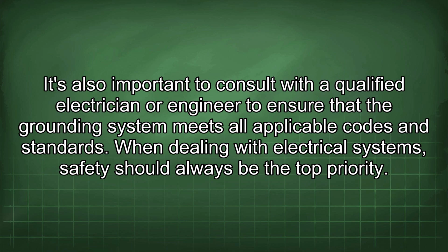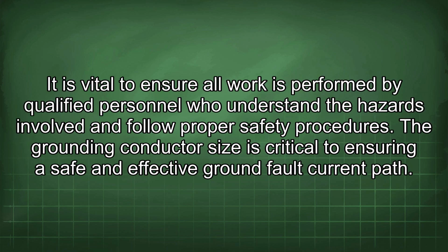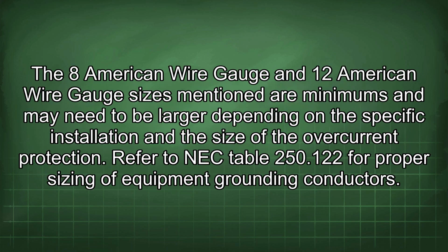When dealing with electrical systems, safety should always be the top priority. It is vital to ensure all work is performed by qualified personnel who understand the hazards involved and follow proper safety procedures. The grounding conductor size is critical to ensuring a safe and effective ground fault current path. The 8 American wire gauge and 12 American wire gauge sizes mentioned are minimums and may need to be larger depending on the specific installation and the size of the overcurrent protection.